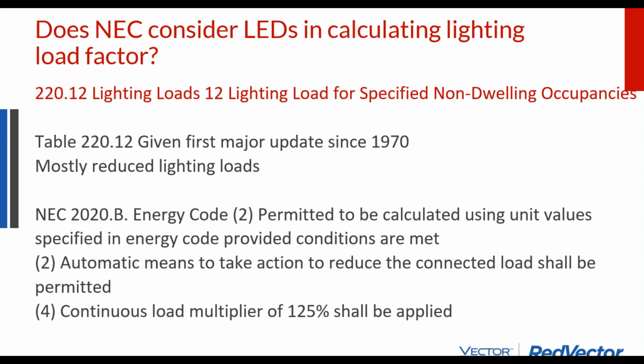So what that means is now with batteries and smart digital controls, we're getting more advanced at being able to kill certain loads when other loads click on. And the National Electric Code, by and large, allows engineers to step in and say, hey, if I'm designing this system and I'm stamping it to say we have a battery and load management system that will limit the power draw of the building to this amount, that can override the tables and charts, so long as you're an engineer making that calculation.